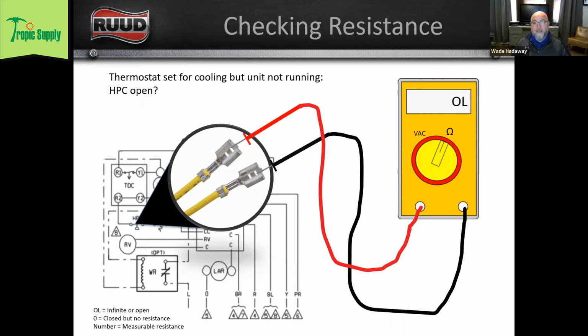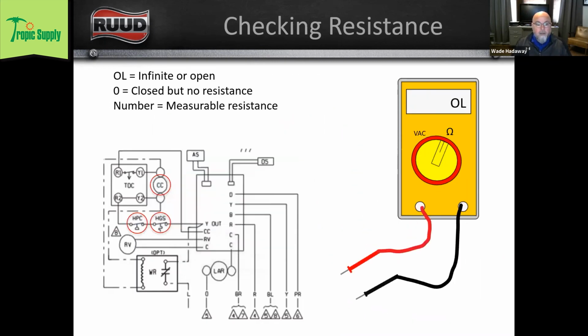We may have a clogged condenser coil. We may have a refrigerant problem. But those are the 2 ways that we can check. We can either hopscotch to figure out which is the open switch, or we can disconnect those switches and check across each one and see what our resistance is. So I'm not going to go any further and check across my contactor, but I could. You would expect to see some resistance across your contactor coil. Typically, if you have a coil that fails, it's going to read OL. If you read resistance across your coil, it's probably good.